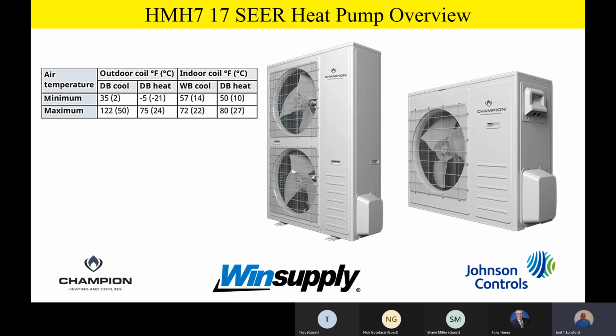And let's face facts, on any heat pump, once you start getting down below about 15, 20 degrees, it starts losing capacity quite a bit, and you'll probably be bringing on some auxiliary heat typically. But it will operate all the way down to -5 on the outdoor coil in the heating mode of operation. And you can also use it to heat the home up to 75 degrees outside, which is going to be pretty warm outside to be running a heat pump, but it still has that flexibility and capability.